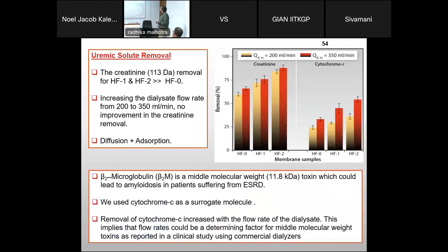And uremic solute removal. So when the hemodialysis is run in a countercurrent flow, by increasing the flow rates, definitely you can change the mass transfer characteristics and you can improve the diffusion. But blood, you cannot increase the blood side flow rate beyond a point. But the dialysis side flow rate was changed from 200 ml per minute to 350 ml per minute.